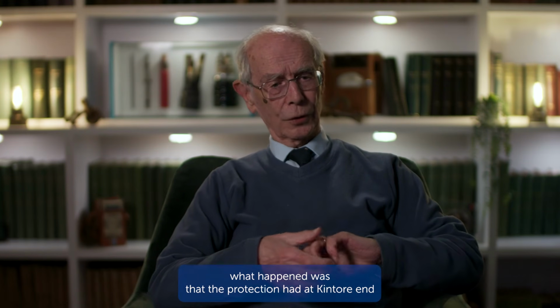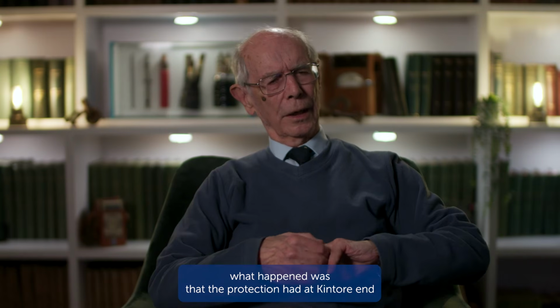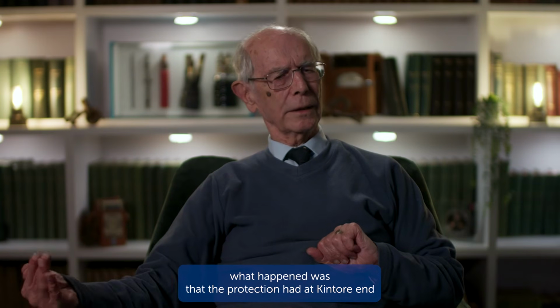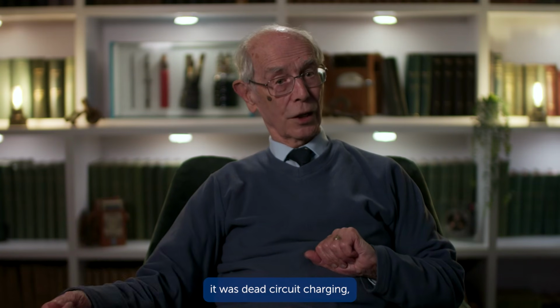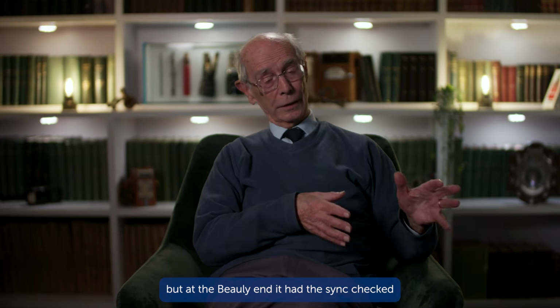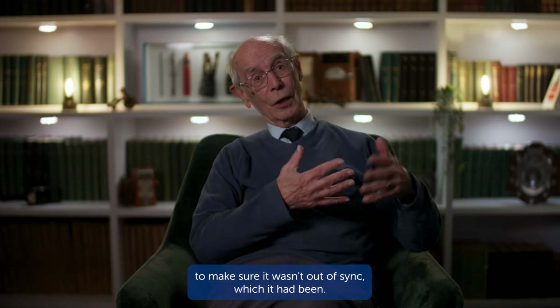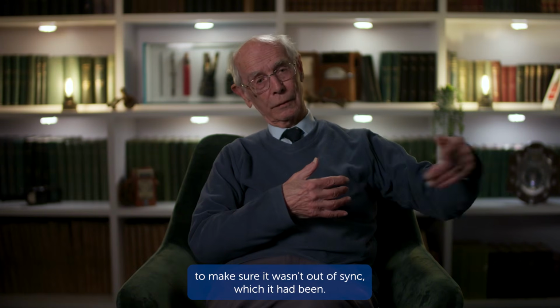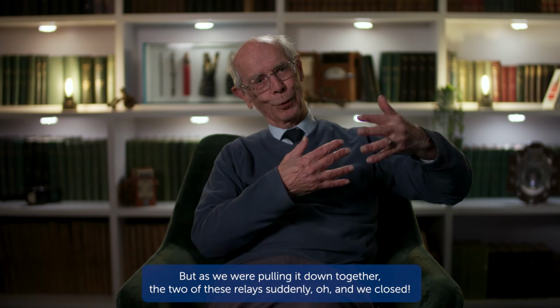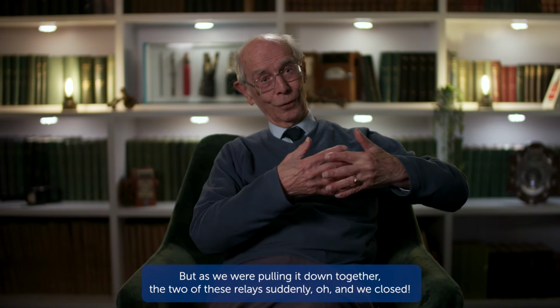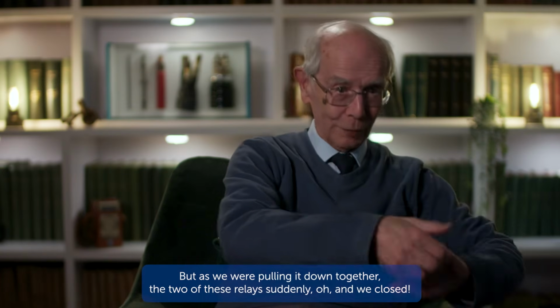What happened was that the protection at the Kintore end was dead circuit charging, but at the Beauly end it had the sync check to make sure it wasn't out of sync, which it had been. But as we were pulling it back together, the two relays agreed, and we closed it.